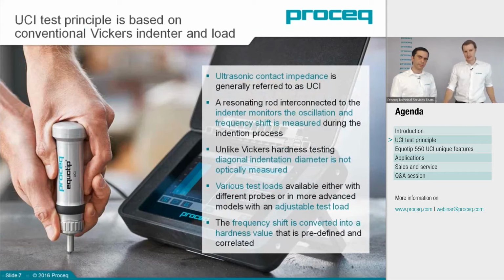So UCI, the three letters, stands for ultrasonic contact impedance, and this describes the method already quite well. The instrument works with a resonating rod, which you can see on the top of the probe, and there a Vickers diamond is mounted and forced into the material to do the hardness test. Unlike the Vickers or the stationary Vickers hardness test, UCI measures a frequency shift, and the frequency shift is measured from the zero frequency when the probe is not in touch with the material, and when the test load is applied.